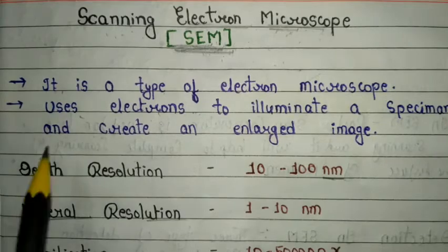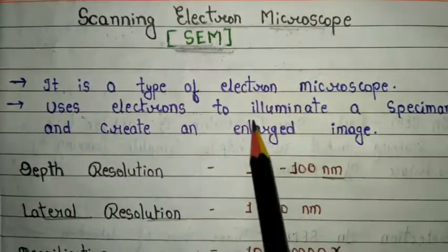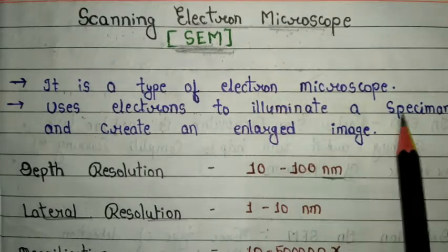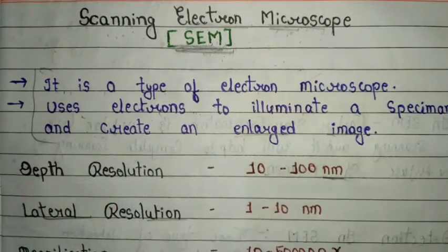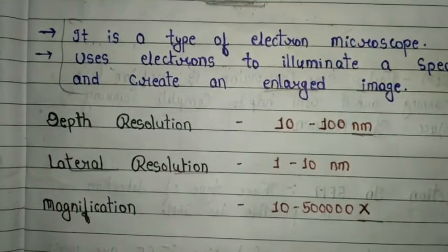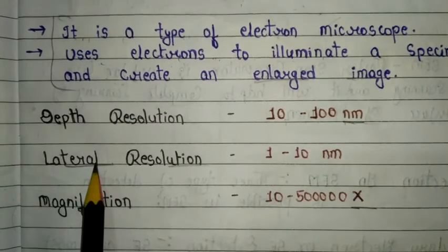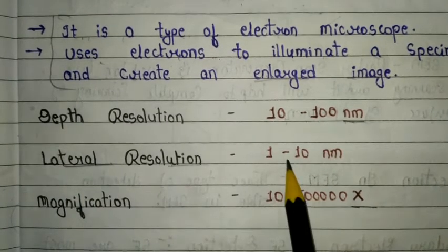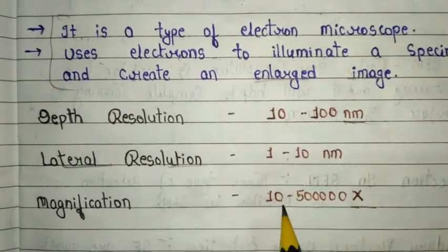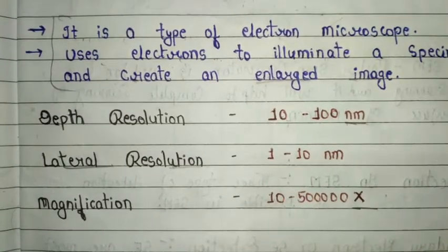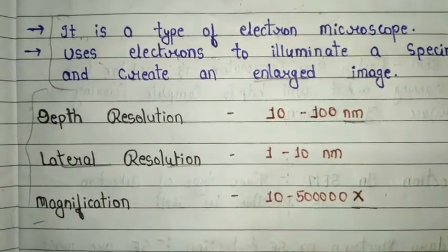The basic introduction of SEM: it is a type of electron microscope that uses electrons to illuminate a specimen and create an enlarged image. The depth resolution of SEM is 10 to 100 nanometers, lateral resolution is 1 to 10 nanometers, and magnification power is 10 to 5 lakh x. These are the basic important points about scanning electron microscope.